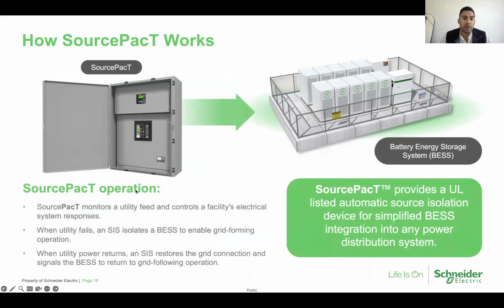So how does SourcePacT work? So SourcePacT comes with the motor operated breaker. And you see that there on the enclosure. That's on the bottom half, and the top half has a SourcePacT controller. And this controller monitors the primary service, so it's monitoring voltage and frequency. And when it detects an abnormality or outage, depending on the parameter set, it will send a signal to the motorized breaker to open. At that point, we're opening and safely disconnecting from the primary service. That could be at the service disconnect, that could be downstream from your main switchboard.